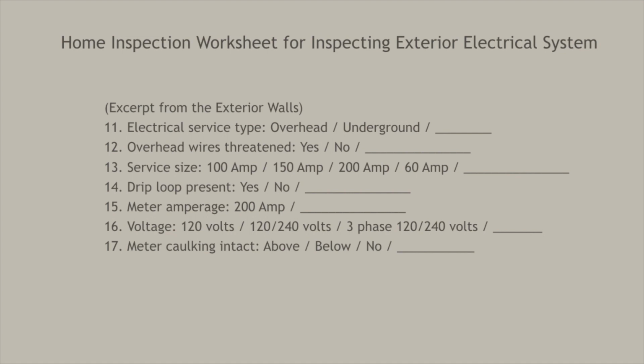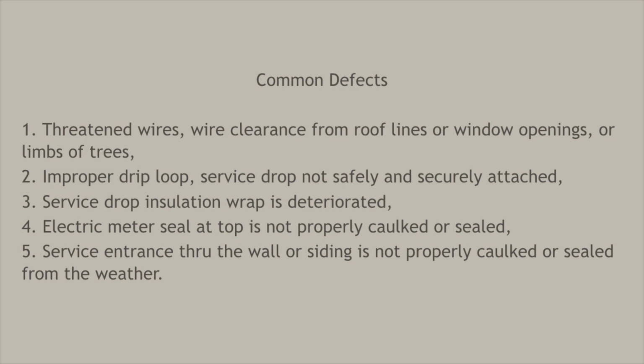Here are the checklist items to inspect that you saw in the exterior walls lesson. You will inspect these elements of the electrical system when you are outside inspecting the walls. Some common defects that may be observed when inspecting the exterior electrical system are threatened wires, wire clearance from roof lines or window openings, or limbs of trees. Improper drip loop, the service drop not safely and securely attached. Service drop insulation wrap is deteriorated. Electrical meter seal at top is not properly caulked or sealed. Service entrance through the wall or siding is not properly caulked or sealed from the weather.